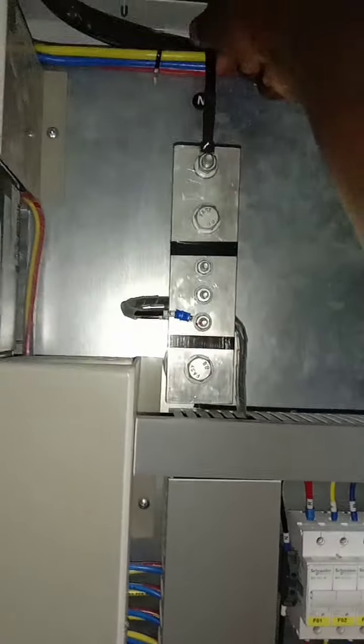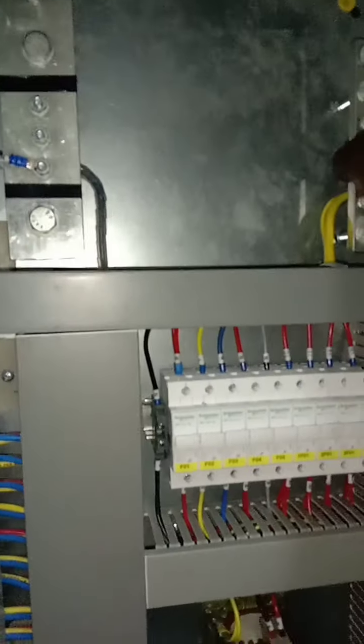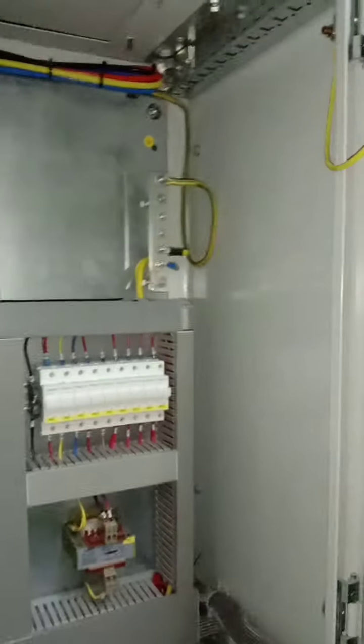Of these two bus bars, the first one is for neutral, as you can see here. So the incoming supply comes, the neutral will be terminated here, and then on the other side will be the earth bus bar. As you can see, this is the earth indication. Then the earth conductor will be terminated on the other side. As you can see, termination is already done.